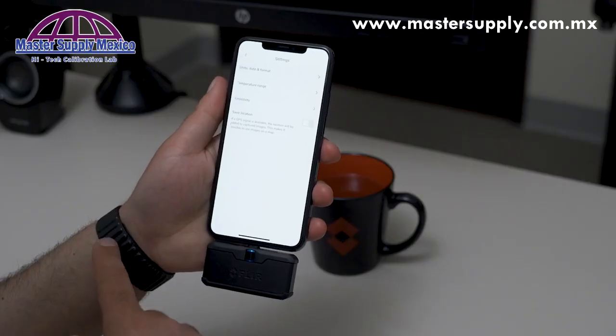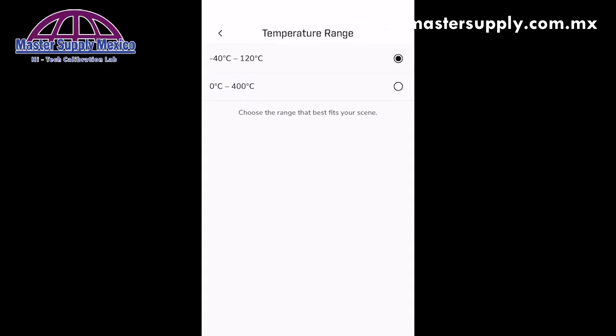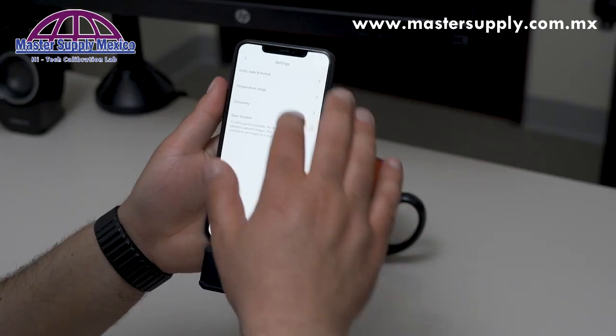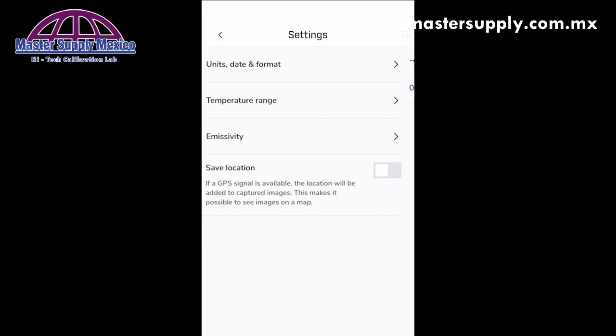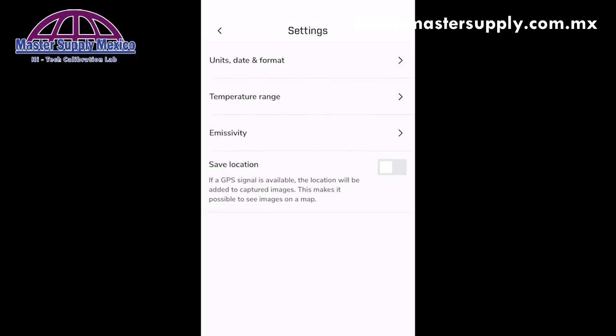With compatible FLIR ONEs, you're able to also toggle temperature range into a high gain mode. For example, you can switch from 0 to 400 degrees Celsius. The app also allows you to change to different preset emissivities. And finally, you're able to toggle whether or not you want to save location to your thermal images metadata.